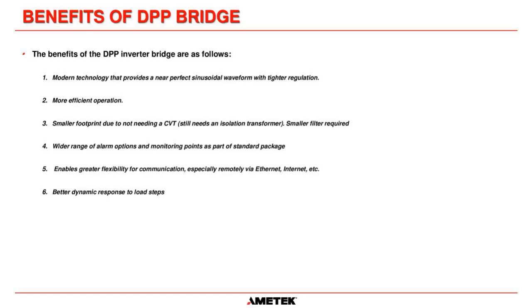It has a wider range of alarm options and monitoring points because it's all electronics—we can do so much more with a PWM system. It also enables greater flexibility for communication, especially via Ethernet, internet, SCADA, and DCS. Our DPP systems are much more modern in design and can communicate easily with each of those options, and have a better dynamic response to load steps, as I mentioned earlier.